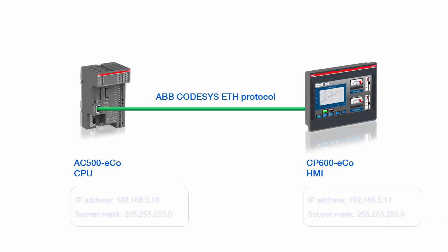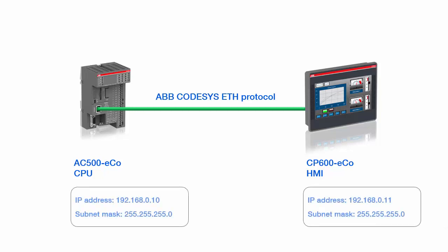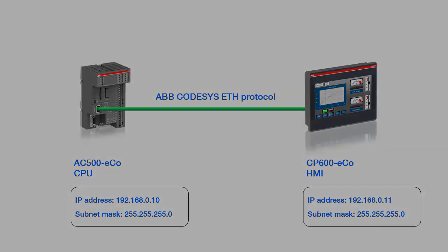It is a must to bring both the PLC and the panel's IP addresses to the same IP group, including the subnet masks. For the AC500 EcoCPU, the IP address configured by default will be used. For the CP600 EcoPanel, one needs to define and configure the appropriate IP address directly on panel system settings.